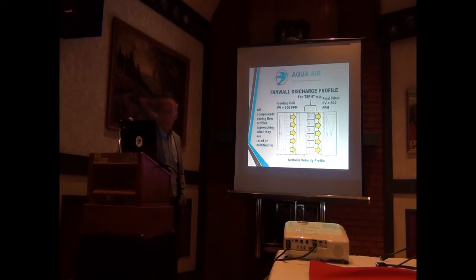And if you look at downstream, same thing, the profile is very even. This is like pushing a big wall of air through the air handler. And you don't have those high turbulent velocities that you would have with one giant fan. So here you're going to maximize the effectiveness of your coil. By doing so, your boiler load and your cooling chiller load are going to be less, which would equal more efficient operation of your system, and also would save you money in the long run with your energy costs.